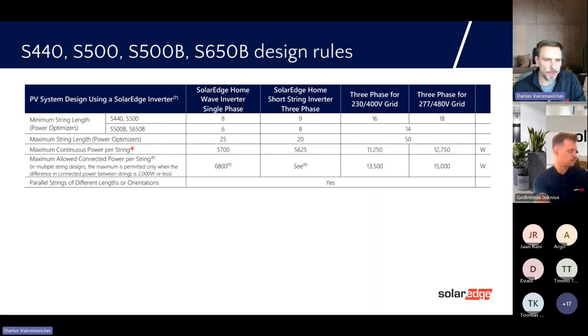Of course, we have a maximum string length, or a maximum quantity of optimizers per string, and maximum power per string as well, for each kind of inverter. But another important rule is, if we talked before about commercial optimizers and there is a 5 optimizers difference, here we have not a quantity of optimizers, but the maximum amount of power difference between the strings, which is 2 kilowatts. So the strings cannot differ more than 2 kilowatts from each other.